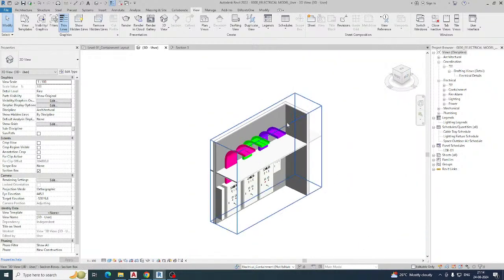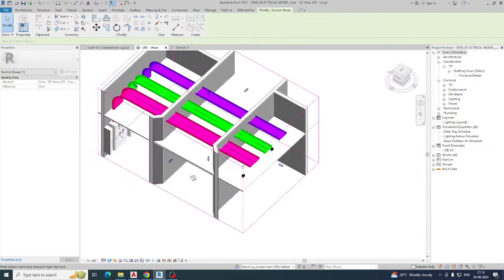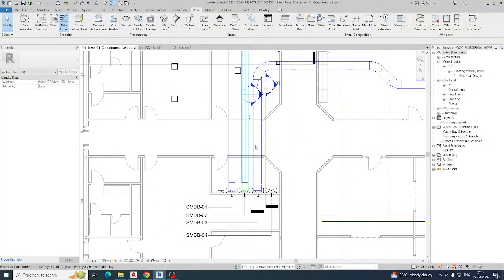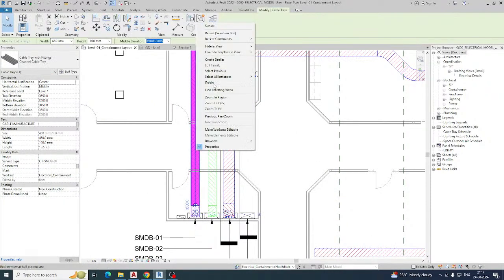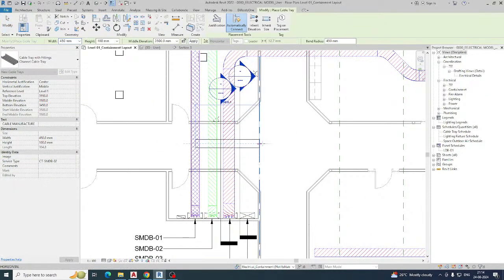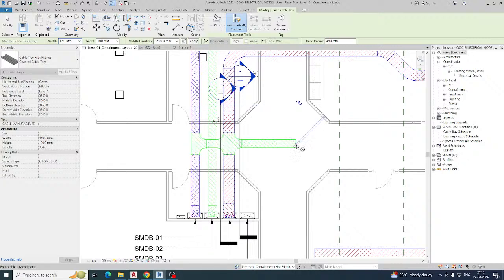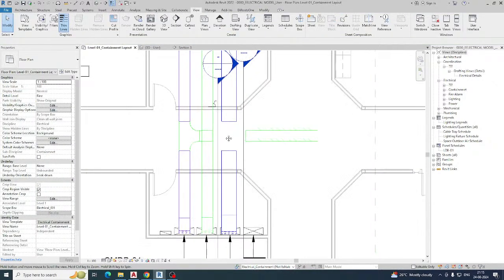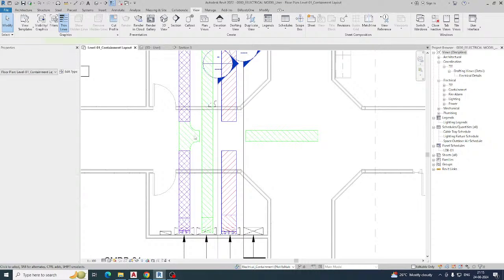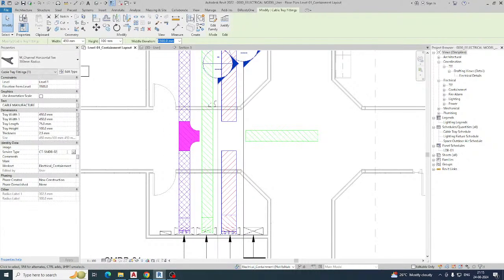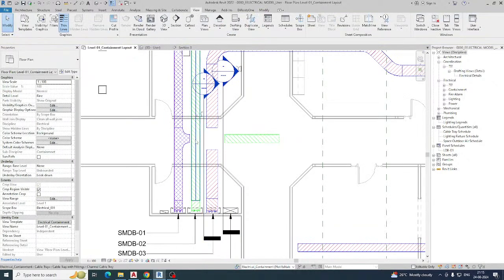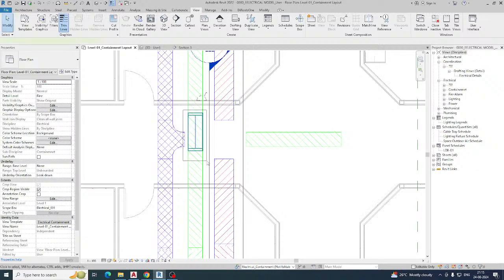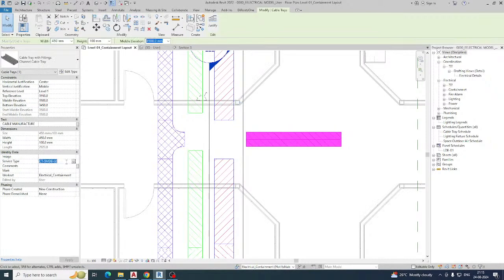These three cable trays are at the same level, so they may clash. If you need to create a branch, use Create Similar, but there will be a clash if they're all at the same height. Delete the clashing elements. To resolve this, create a section view and use the Split command (SL) to split the cable tray where needed.